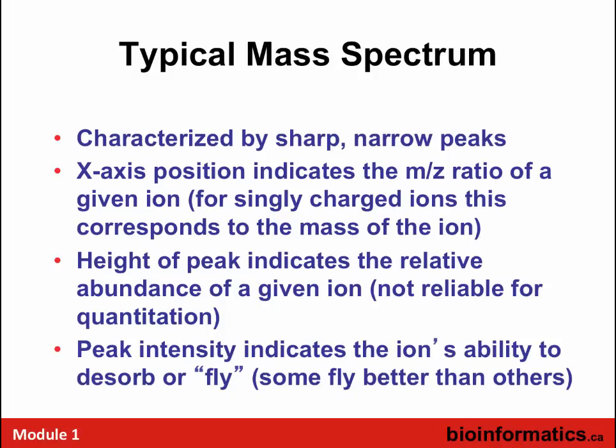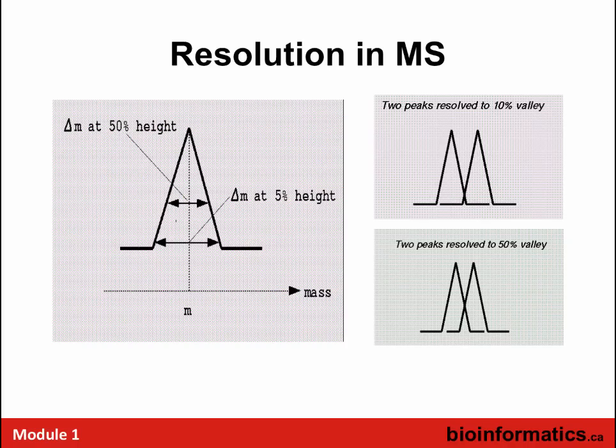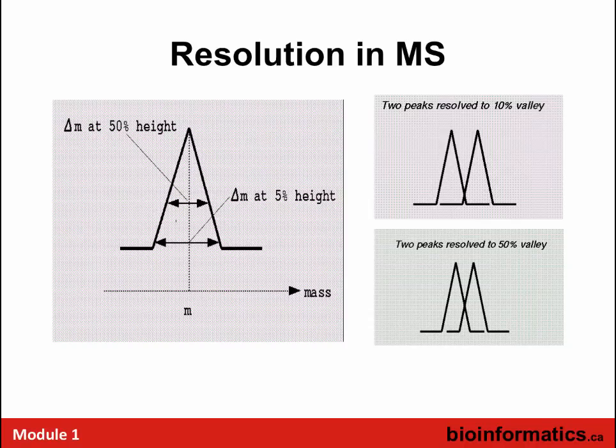Different mass spectrometers have different resolving power — measured by the mass you're measuring and the mass difference between two masses you can separate, equivalent to resolving power in a microscope. A low-resolution linear ion trap has resolution of about one Dalton, and you can barely see isotopic peaks — they all merge. Run the same compound on a high-resolution time-of-flight instrument and you can see all the peaks clearly. This illustrates going from technology of 15-20 years ago to the latest — looking at resolving power, where a resolving power of 1,000 gives a broad blue peak versus 30,000 which gives narrow, easily seen black lines. The better the resolution, the more likely you can characterize the molecule and determine its molecular formula.